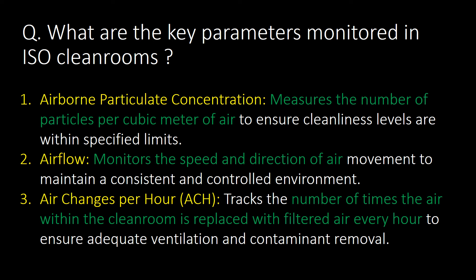What are the key parameters monitored in ISO cleanrooms? The first parameter is airborne particulate concentration — we measure the number of particles per cubic meter of air. The second parameter is airflow — we monitor the speed and direction of air. The third important parameter is air changes per hour (ACH) — we track the number of times the air within the cleanroom is replaced with filtered air every hour.